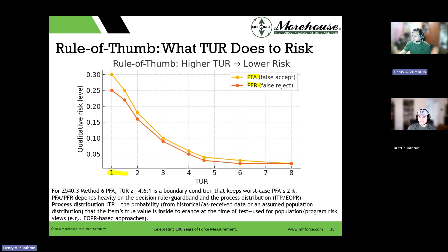There were some mil standards at 10-to-1, 4-to-1. The example I just gave was an actual real-life example where we were 20-to-1 a lot, and that was an .05 measurement. There's a lot of times in our lab where you'll see, and you've seen some of the certificates, 40, 50-to-1. I don't know what it caps out at. Because it is a ratio, the larger that tolerance gets, you're dividing that numerator by this denominator. So if somebody sent us something in for cal and said, I need 10% of full scale, the number would be, and we're at 0.0016%, divided out, I mean, we're talking thousands.